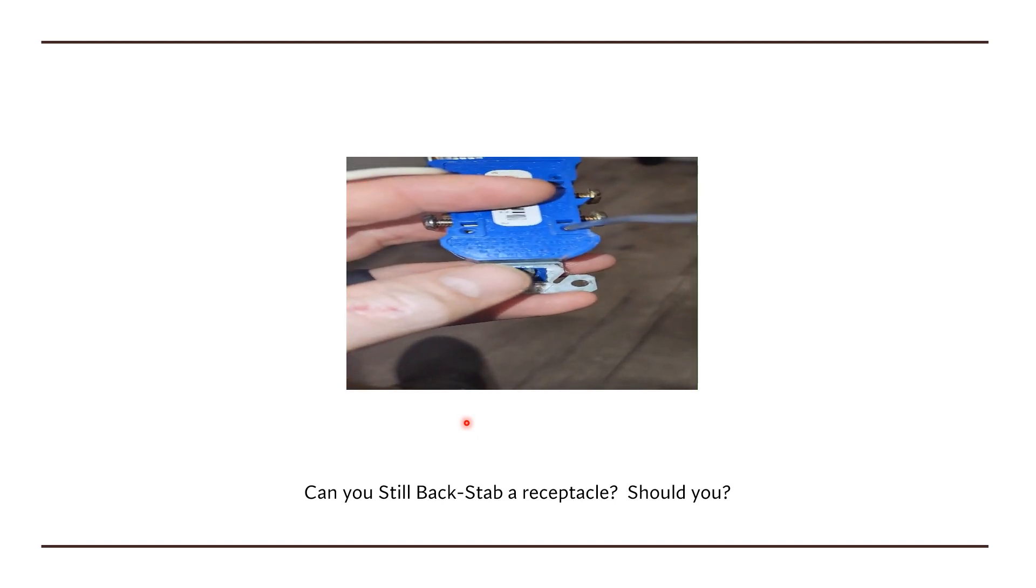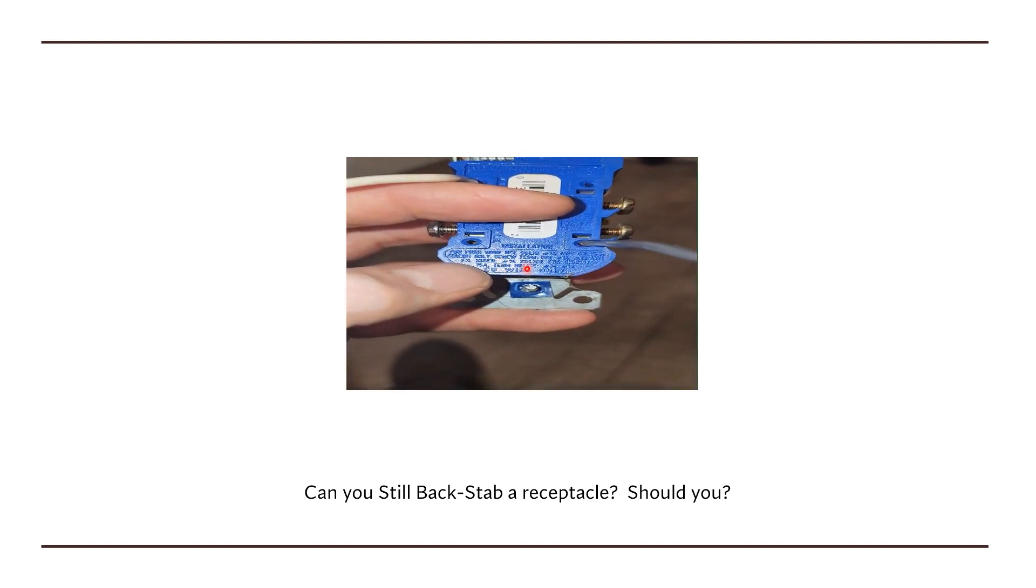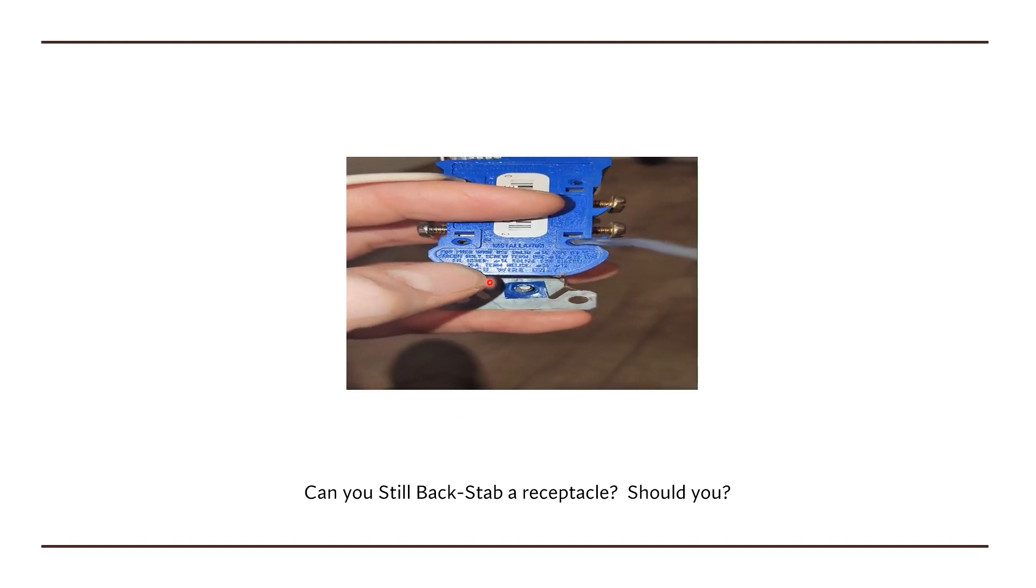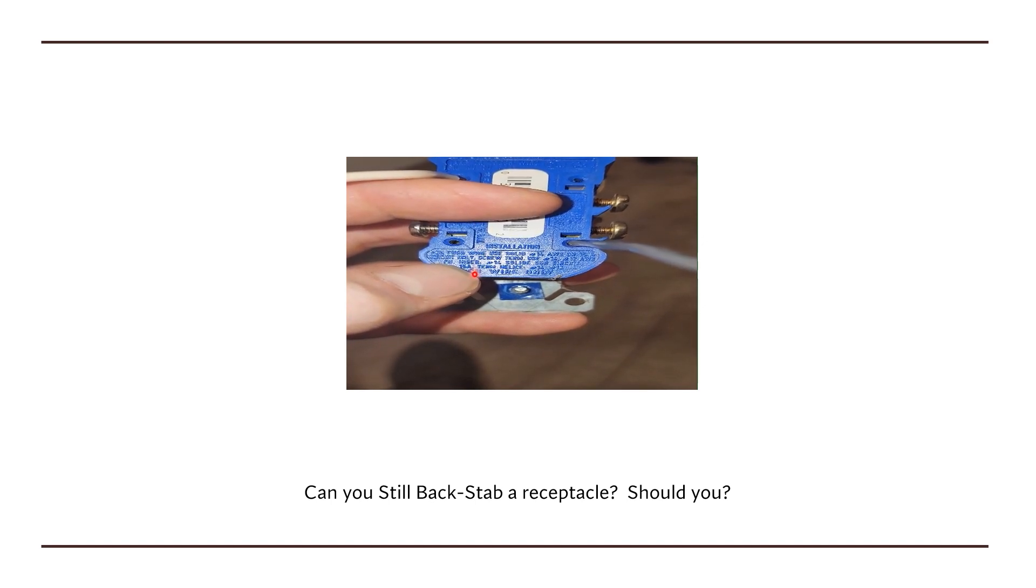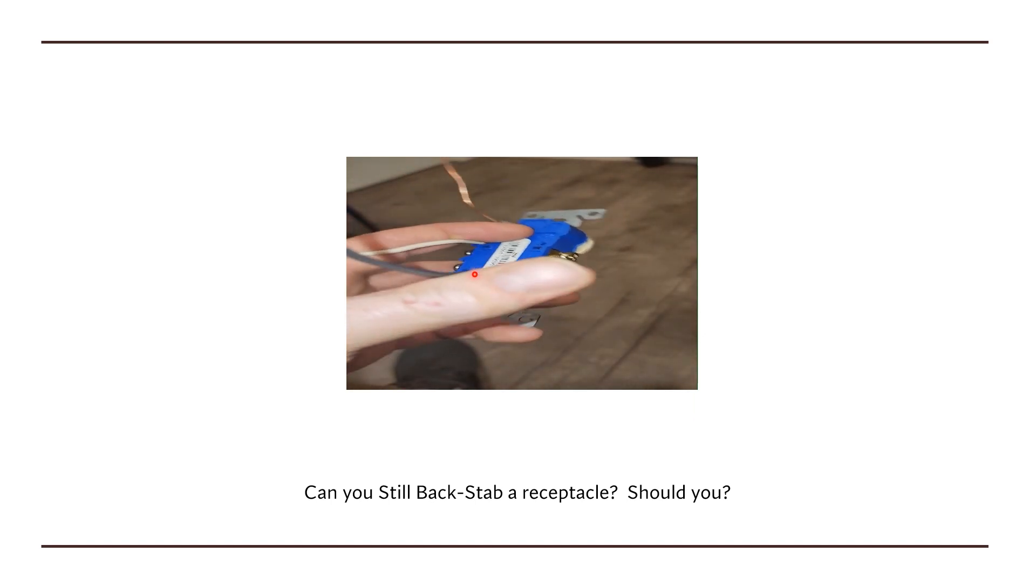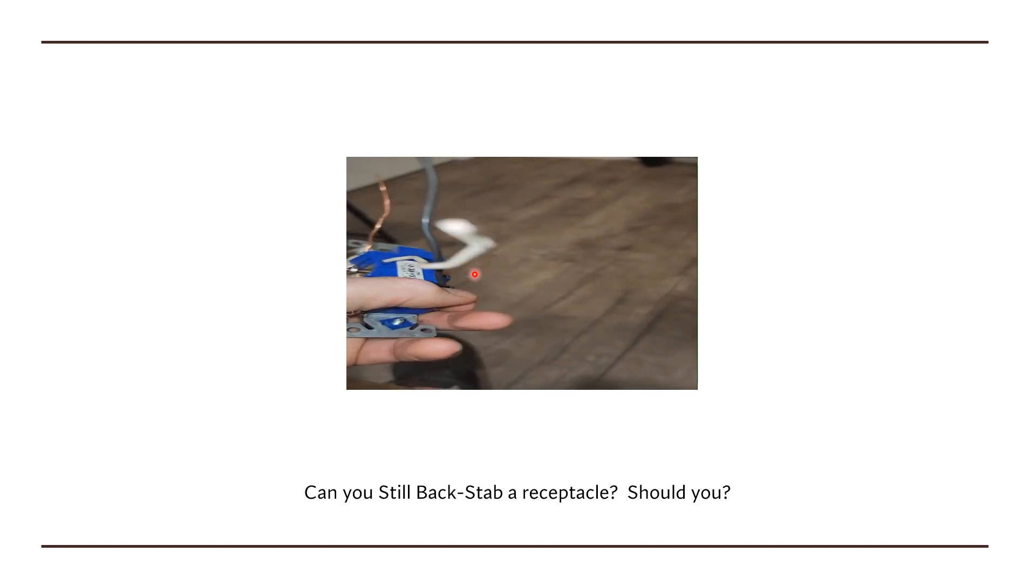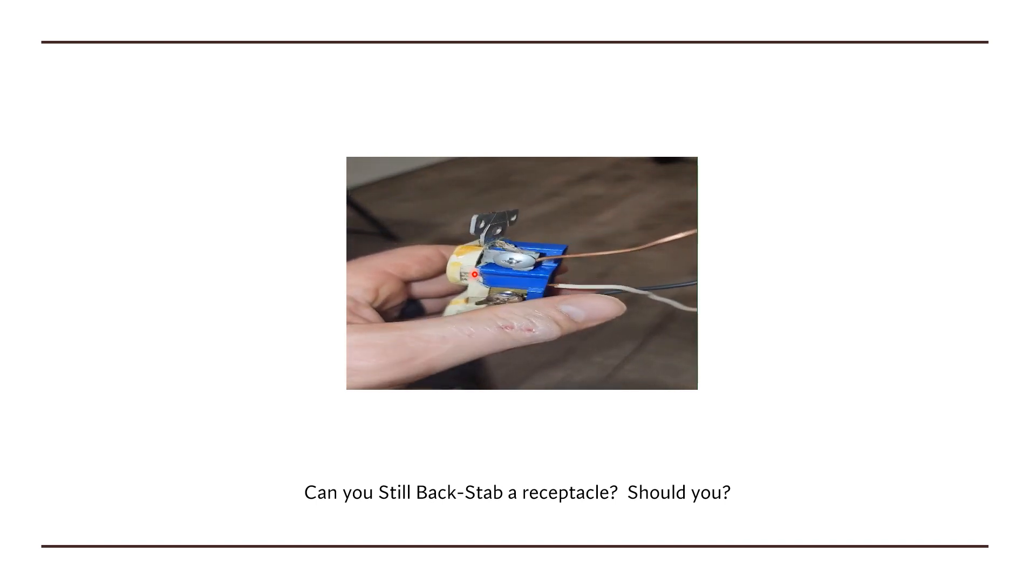Not all of them are listed for 12-gauge wire. Most of them nowadays are only listed, it's in very tiny writing, for 14-gauge solid wire. So the only way you can use the backstab terminals with this device and use it safely is to use it with 14-gauge wire.